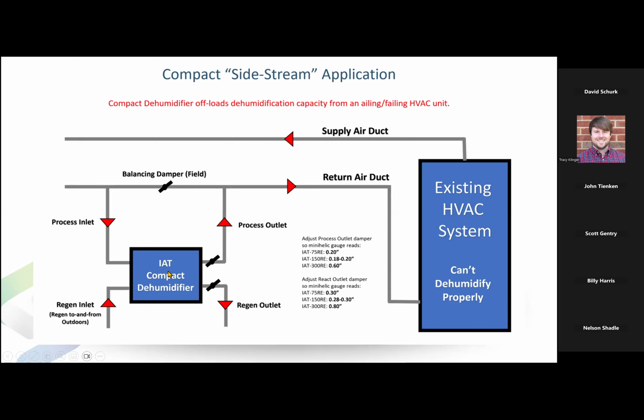We can also provide this as a DOAS and simply dehumidify all of the ventilation air coming to the space, handle the entire outdoor air latent load and the indoor latent load, and then make whatever it's feeding downstream sensible cooling only, maybe sensible cooling, heating, filtration, humidification, whatever. Just a great way to optimize the system from a first cost perspective and get the results that you want. Playing in the gray area, sometimes even lower.